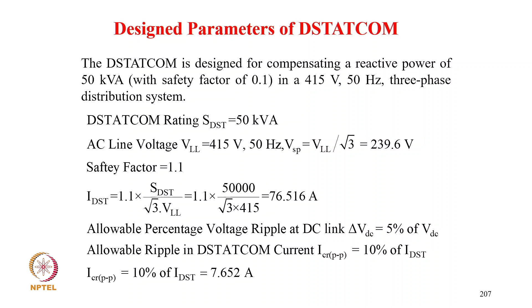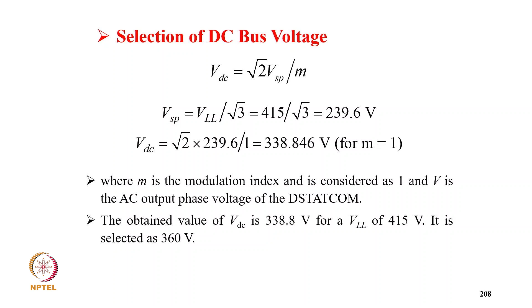Allowable percentage voltage ripple at DC link, delta VDC, is 5% of the VDC, and the allowed ripple current in DSTATCOM is 10% of DSTATCOM current. So ICR equal to 10%, that is 7.652 ampere. So VDC equals root 2 VSP upon M. Putting a value, it comes to typically 338.846 volt, where M is the modulation index and is considered as 1, and VSP is the AC output voltage per phase of the DSTATCOM. So the obtained value of VDC is 338 volt for VLL 415, and it's selected as 360 volt.